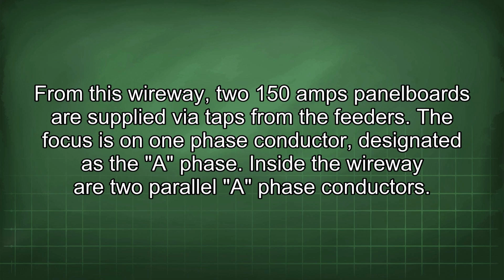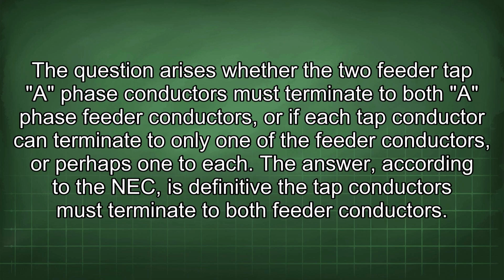The focus is on one phase conductor, designated as the A phase. Inside the wireway are two parallel phase conductors. The question arises whether the two feeder tap phase conductors must terminate to both A phase feeder conductors, or if each tap conductor can terminate to only one of the feeder conductors, or perhaps one to each. The answer, according to the NEC, is definitive. The tap conductors must terminate to both feeder conductors.